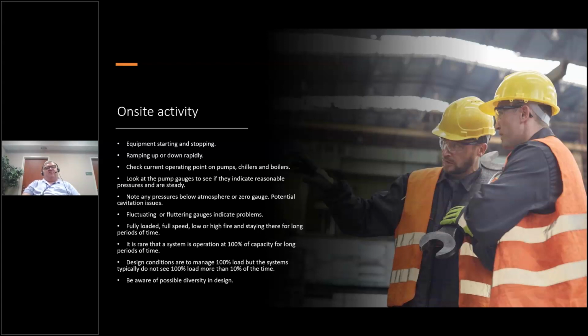And also be aware of diversity in design. I promised John I wasn't going to use these technical terms, but diversity basically says that since we rarely run at 100% load, we could probably get away with designing to 80% design. And that's happened in the past. And if you don't realize that's what's going on, you'll run into that when you're expecting, okay, I need this many tons or this much GPM, but we're not sized for that.